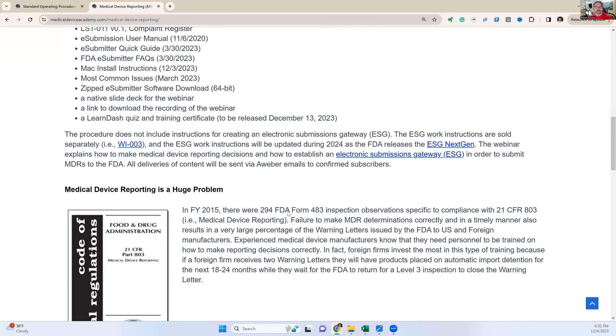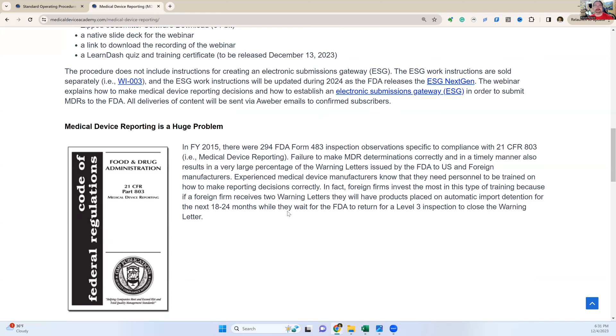We explain on the page why medical device reporting is such a huge problem — it's one of the number one reasons why companies get FDA 483 inspection observations. A lot of companies don't even realize they're responsible for reporting and don't realize they need an electronic submissions gateway. Even companies that think they have a low-risk device and no one will ever get seriously injured — it doesn't matter. The FDA still wants you to have an electronic submissions gateway and a process in place so you could report something if you had to.